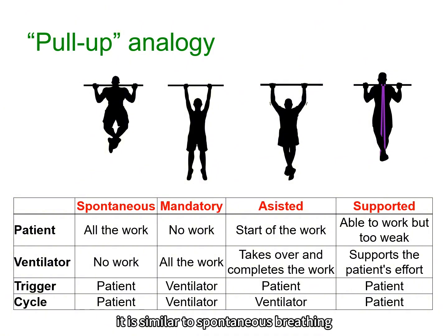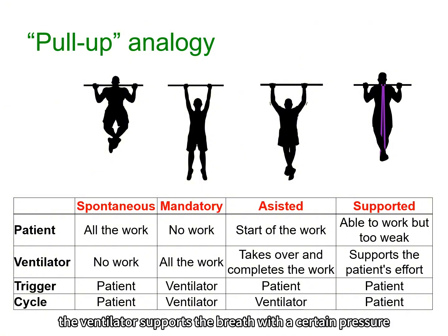It is similar to spontaneous breathing. The patient will initiate breathing and complete some or most of the work, but the effort is weak and tidal volume is not enough. The ventilator senses the beginning and the end of each inspiration by measuring inspiratory pressures and flows. Exactly during spontaneous inspiration, the ventilator supports the breath with certain pressure.